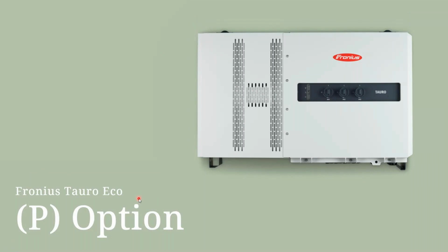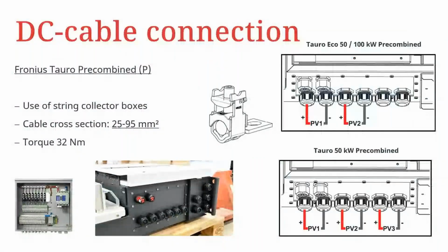Let's now talk about the Tauro Eco P option, P for the pre-combined option. In the pre-combined option, like I've mentioned earlier, this involves the use of DC combiner boxes. As you can see, let's have a look at it down here. Your PVs go in from one terminal, and then from the breaker, the protection breaker, you're going to have larger dimension cables coming out that are the input to the inverters.